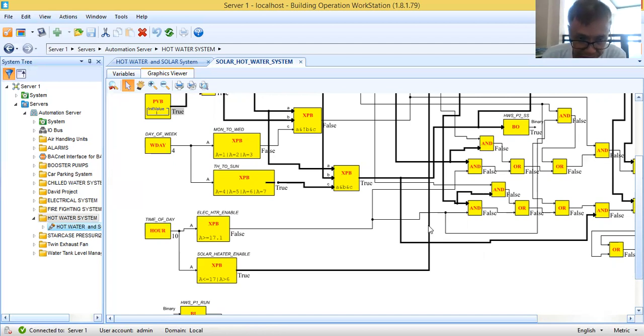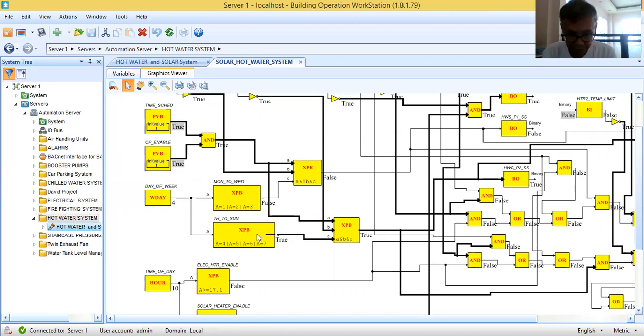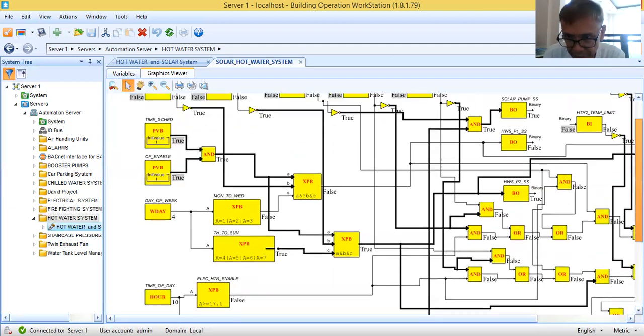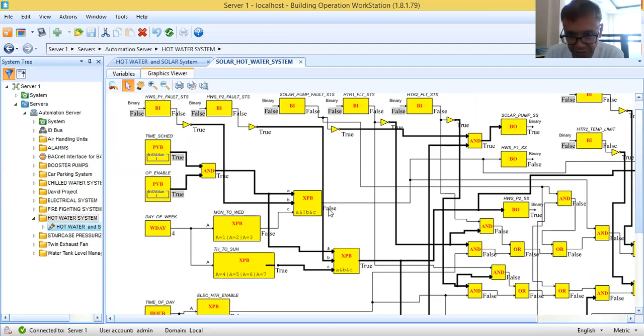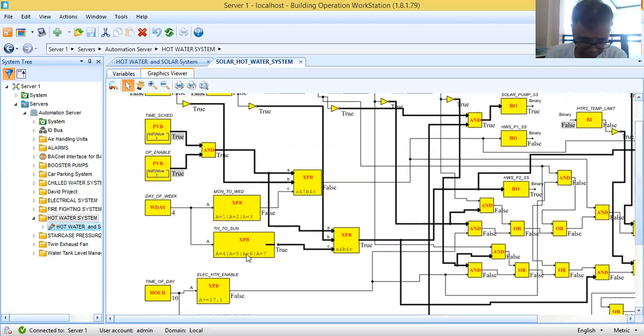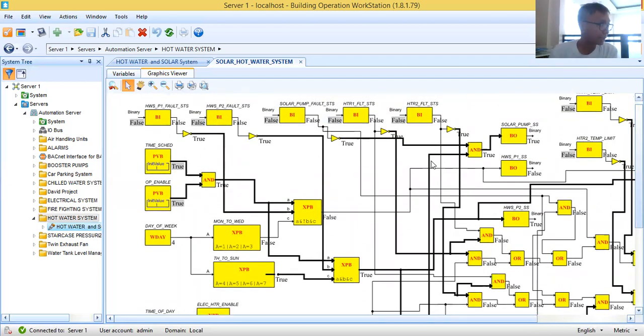I also implemented the day of week to do the sequencing or rotation of my hot water pumps. Monday to Wednesday I run pump one, Thursday to Sunday I run pump two. But I also consider failover: if today is Wednesday and pump one trips, pump two should kick in. Likewise, if today is Thursday and pump two trips, pump one should kick in. As a BMS engineer you should take care of that scenario.